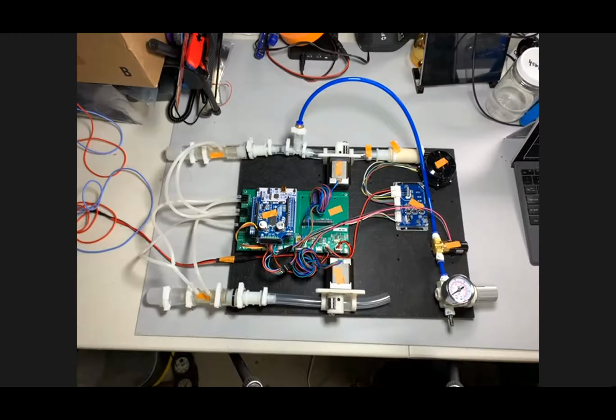Martin asks, should there be a check valve just downstream of the blower to prevent oxygen backflow? Yeah, that's something we had earlier in the pneumatic design and isn't represented here. The reason is we've had trouble with the cracking pressure and chattering of the check valve. We haven't yet found a check valve that meets our needs, so we've removed it for now.